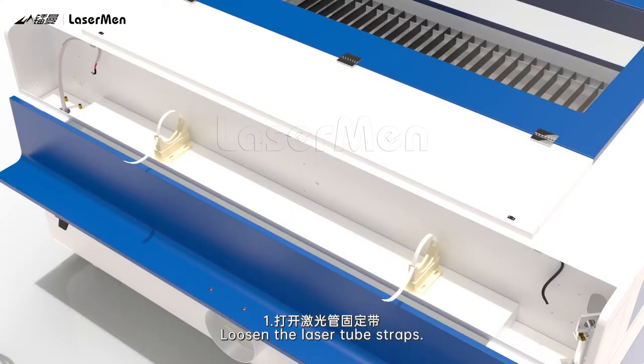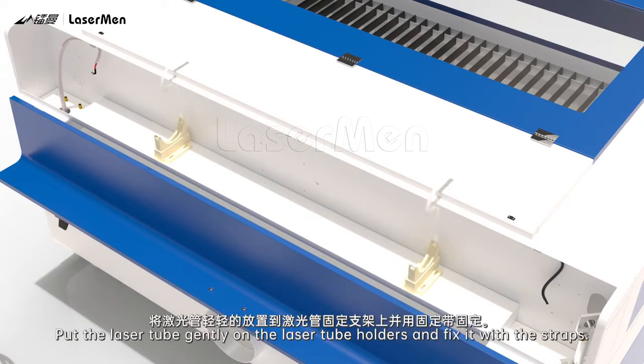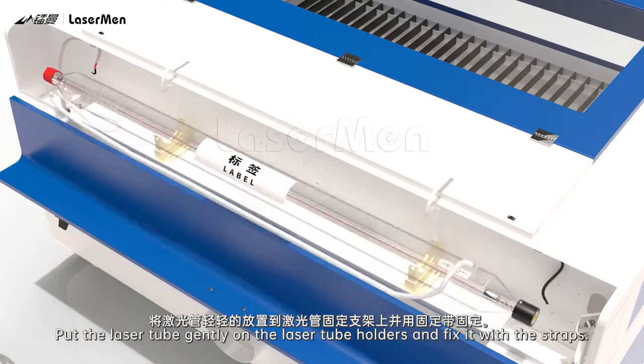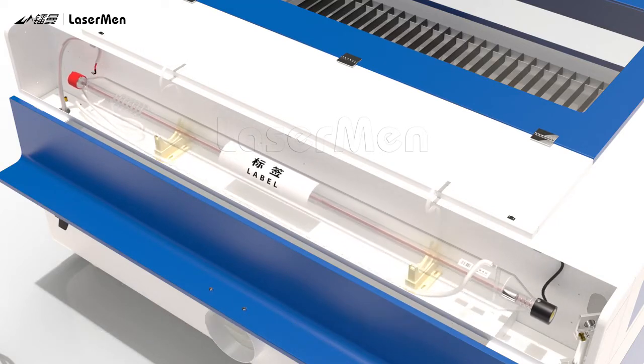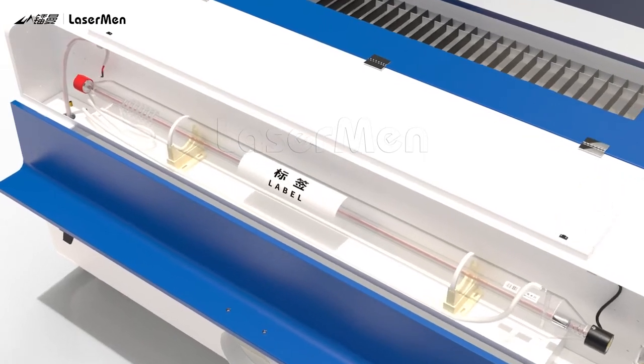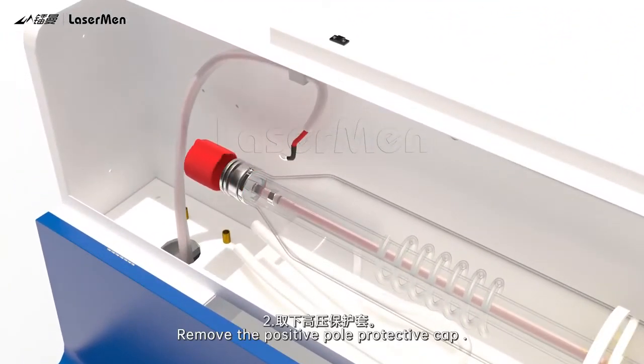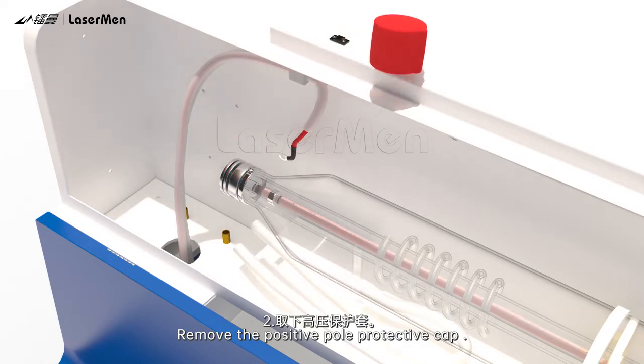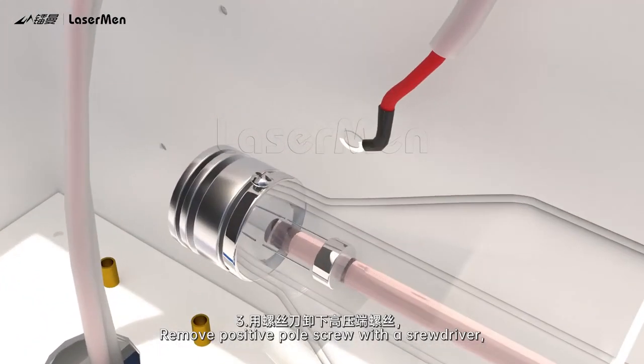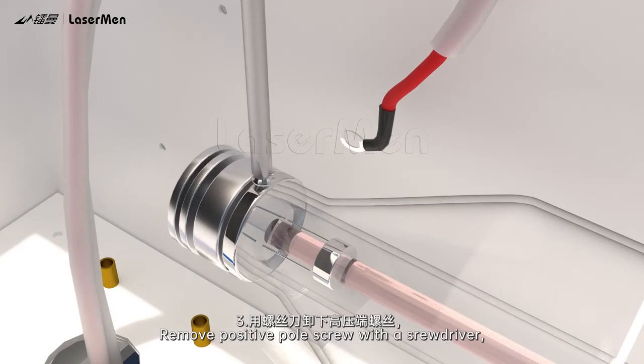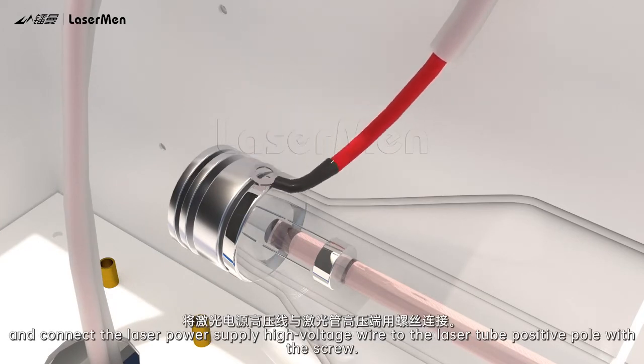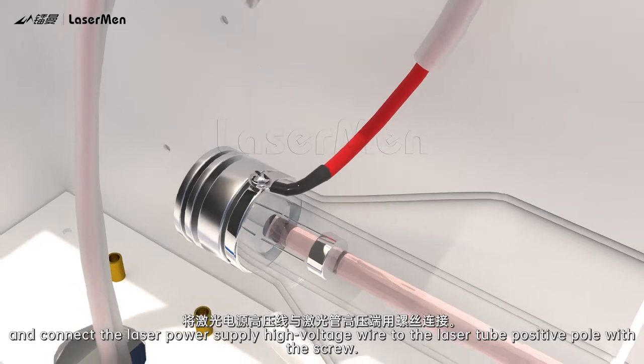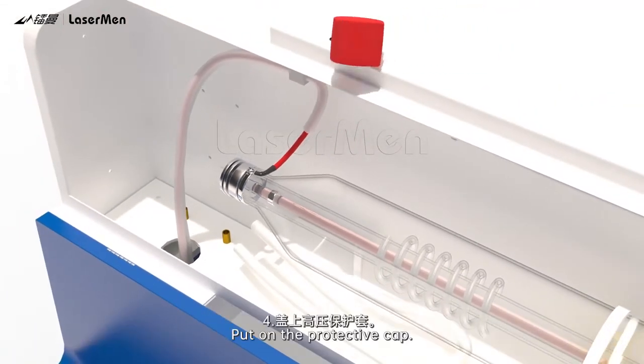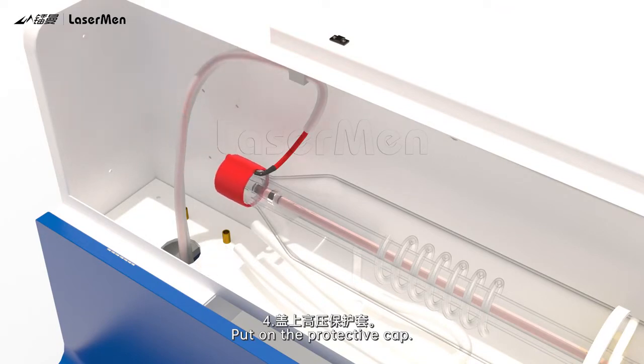Laser tube installation. 1. Loosen the laser tube straps. Put the laser tube gently on the laser tube holders and fix it with the straps. 2. Remove the positive pole protective cap. 3. Remove positive pole screw with a screwdriver, and connect the laser power supply high voltage wire to the laser tube positive pole with a screw. 4. Put on the protective cap.